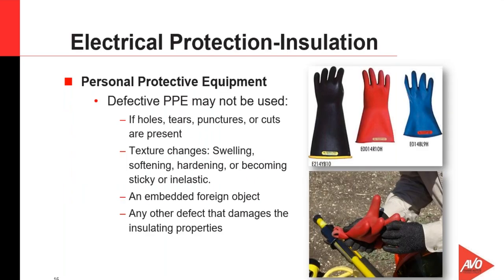In the PPE world, we have several things to consider, rubber gloves obviously being one of the primary. And these rubber gloves have to be rated, they have to be tested, we have to have an in-service care and use program in the company safe work practices to actually use these. The worker, when they receive gloves, needs to demonstrate that they understand how to do the daily inspection. And we're looking for holes, tears, punctures, cuts, or any type of texture change or anything else that appears to be damage in the glove. Scuff marks sometimes can be fairly deep.